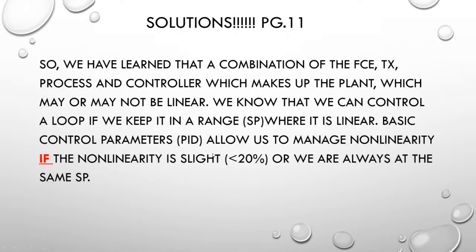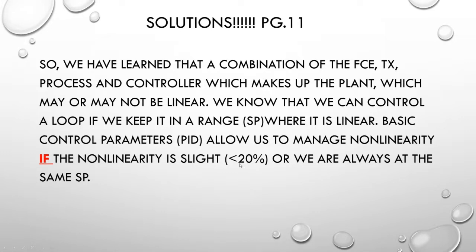So how do we deal with all the potential non-linearities from a process, a valve, or a transmitter? The combination of these things makes up a plant, which may or may not be linear. We know that we can control the loop if we can keep it in a range where it is linear or where we're aware of how it's functioning. Basic PID settings can allow us to manage some non-linearity if it is slight — the ILM states that if it's less than 20% non-linearity, we can generally control it with a PID controller. Or if we're always at the same set point, it should work just fine.